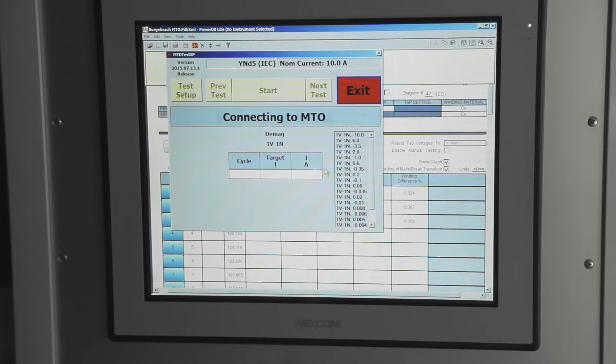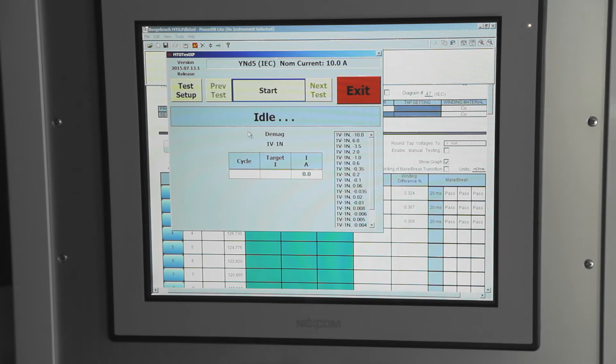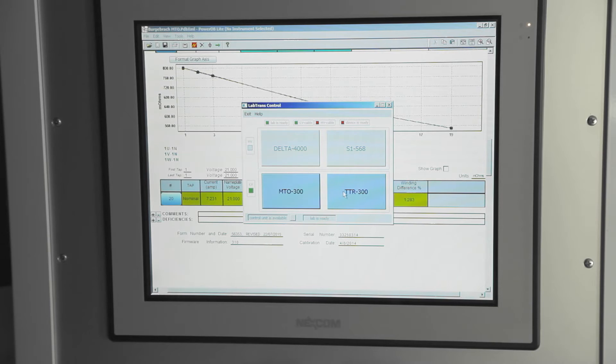Certain tests are sensitive to core magnetization, so demagnetization should be performed after measuring the winding resistance and before returning it to service.